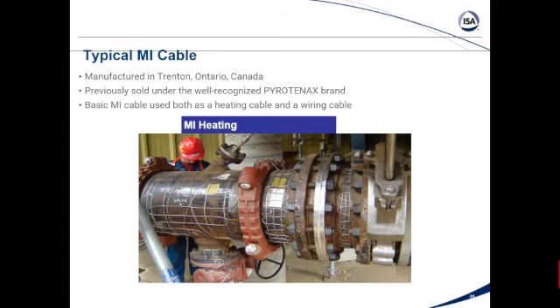So then I'll get into the next major technology, especially in the power industry, which is our mineral insulated cable. And basically this is a metal and magnesium oxide is the only thing that's going on in here. There's no plastics, there's no rubber, there's nothing in there. So basically, when we make this cable, it starts out with, say, a 1/2 inch or a 3/4 inch diameter pipe, heavy wall, and inside there's a 12 gauge conductor, and we extrude it, and we pull it out, and we stretch it over and over again, until the outer diameter and the inner element, that 12 gauge conductor, becomes very, very small, 18, 20, even 22 gauge wire. It can be as thin as a hair.